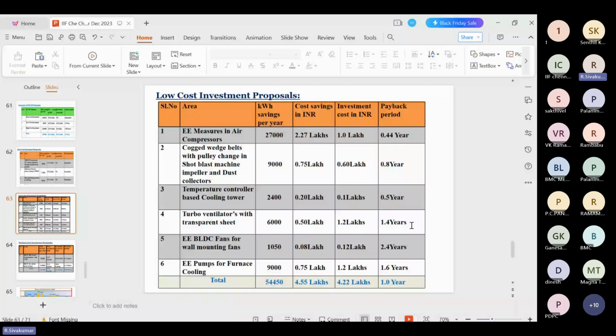And energy efficient BLDC fans for wall mounting fans. Many wall mounting fans of 100 watts and 200 watts are in use. They can be replaced with brushless DC motor wall mounting fans. Almost 1,050 units can be saved. Similarly, the furnace cooling pump can also be changed. All put together, 6 proposals are given in the low cost investment. The unit saving is 54,450 units, 4.22 lakhs is the investment, 4.55 lakhs is the cost saving, and the payback period is 1 year.